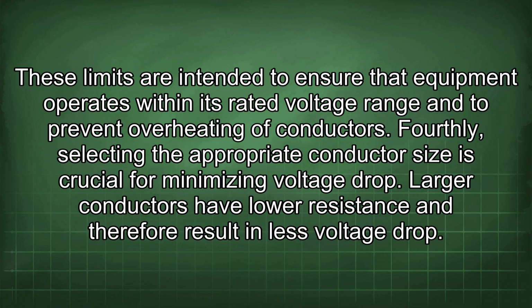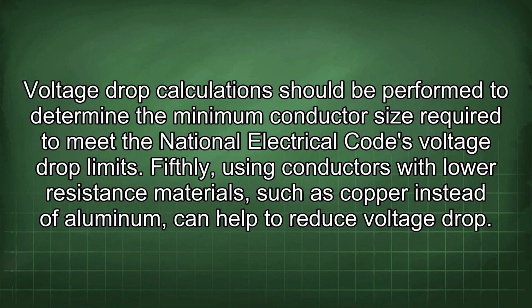Fourthly, selecting the appropriate conductor size is crucial for minimizing voltage drop. Larger conductors have lower resistance and therefore result in less voltage drop. Voltage drop calculations should be performed to determine the minimum conductor size required to meet the National Electrical Code's voltage drop limits.